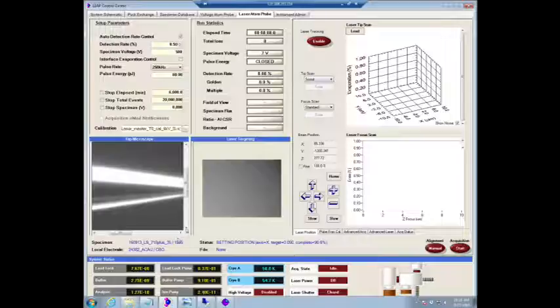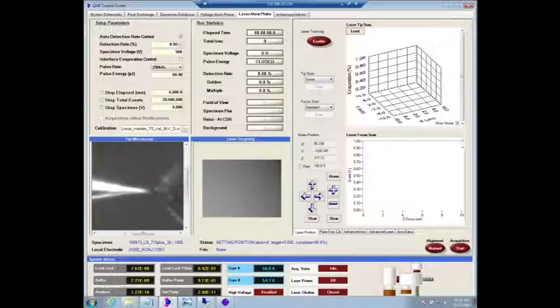Okay, so one thing we'll check is, of course, we've got a specimen in there, so that's all good. And the next thing, of course, is settings. So in voltage mode, you don't have that many settings. The most important setting is the detection rate. The specimen voltage always starts at 500 volts, but if you interrupt your measurement for some reason, you can just resume at the voltage that you stopped at, okay?